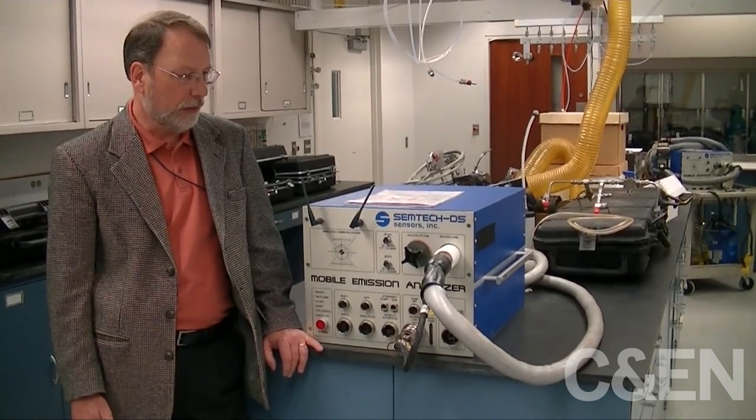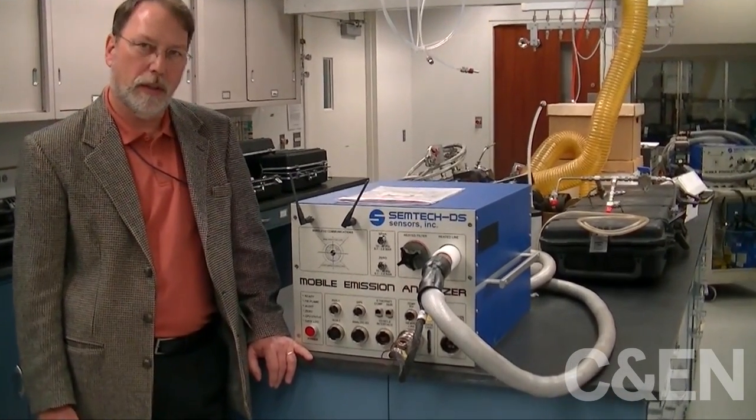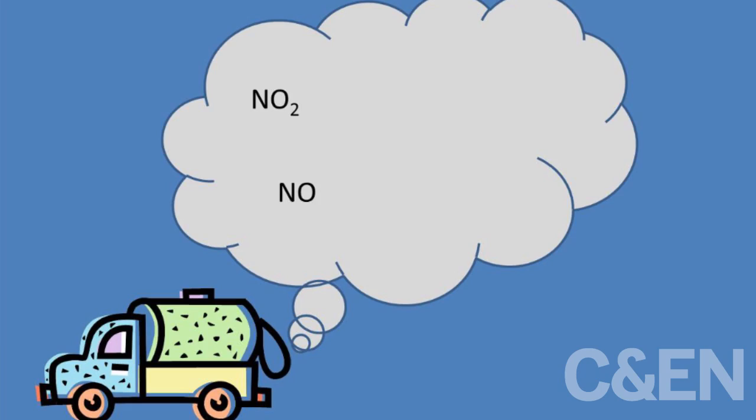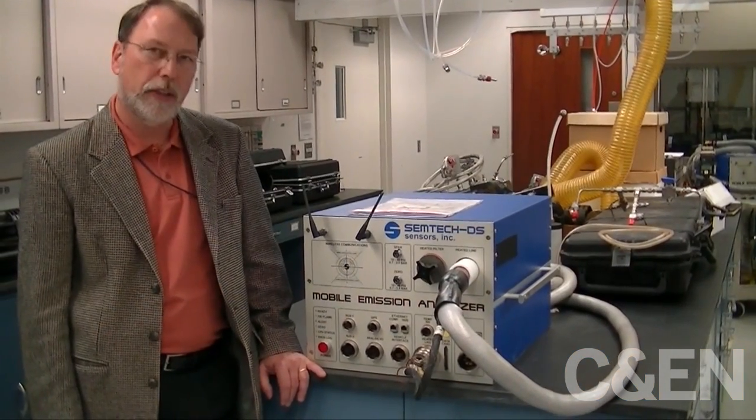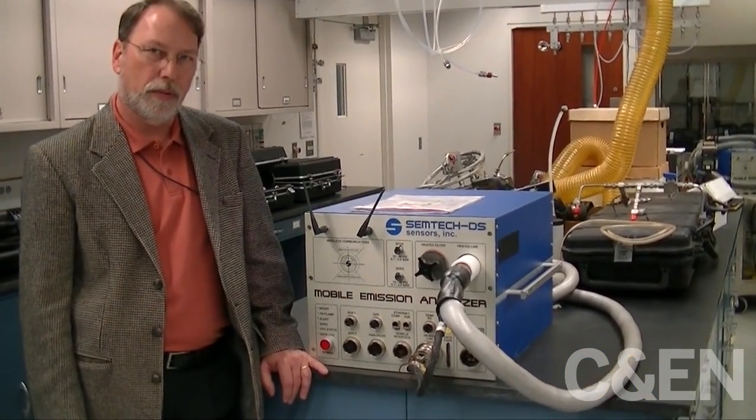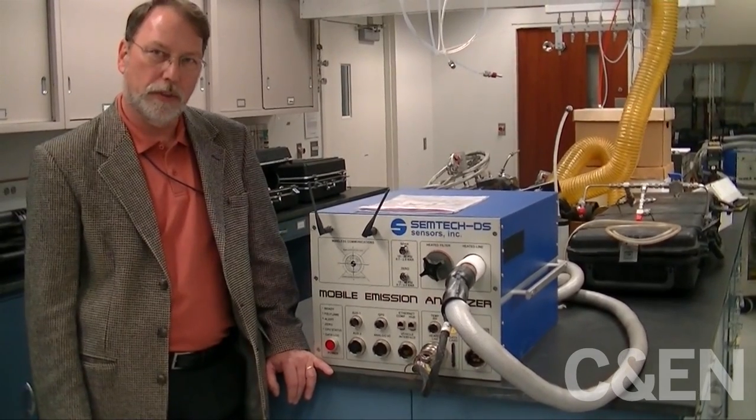The Semtech DS uses non-dispersive infrared technology. It has also a UV measurement for NO and NO2, the oxides of nitrogen, and it also has on board a portable flame ionization detector for hydrocarbons.